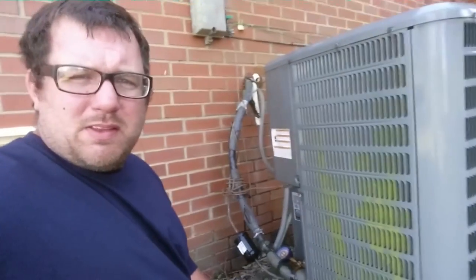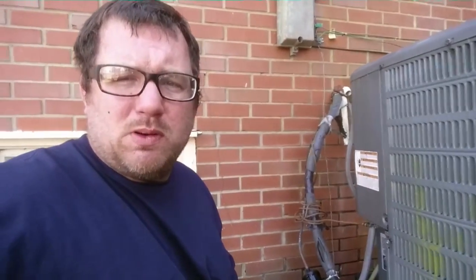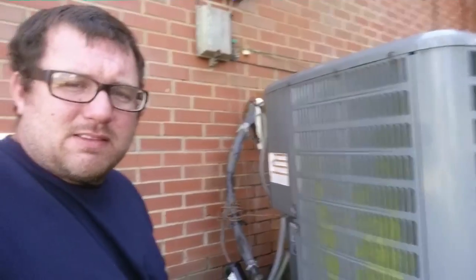I'm sitting here at this Goodman condenser unit because we're going to take a look at a couple different pistons and have a little slideshow of sorts. This Goodman unit was matched up with an old Rheem/Ruud air handler. The Rheem/Ruud air handler has a TXV in it and a piston, and the guys that did this didn't know about the piston with the TXV, so they put in the Goodman piston that came with this condenser. The Rheem/Ruud piston that goes with their TXVs is much larger. We'll take a look at that as a sort of cautionary tale so you guys can see it in the field.